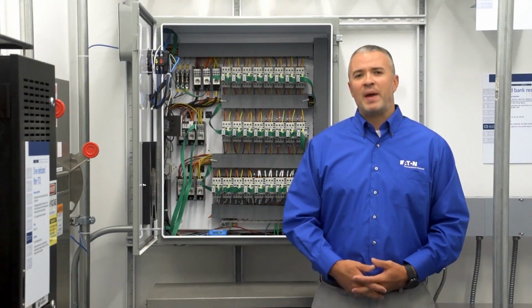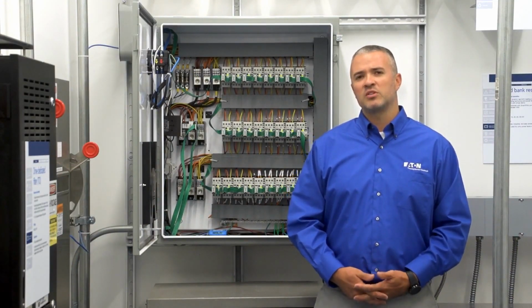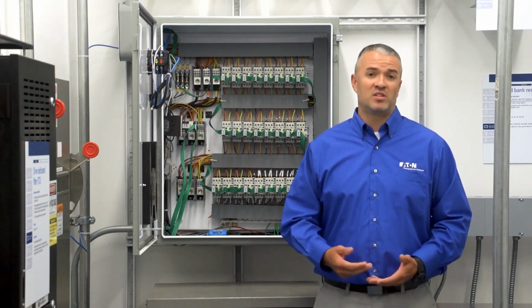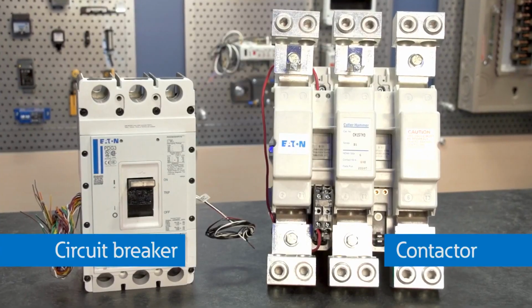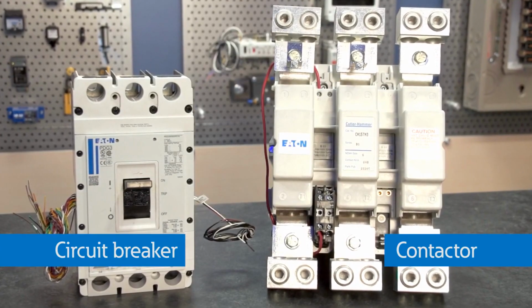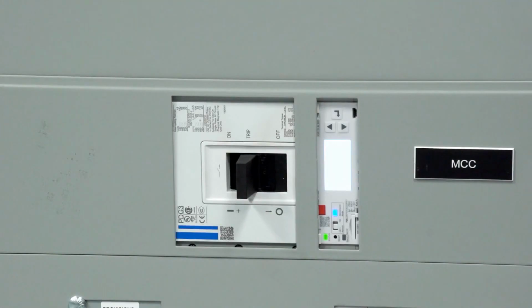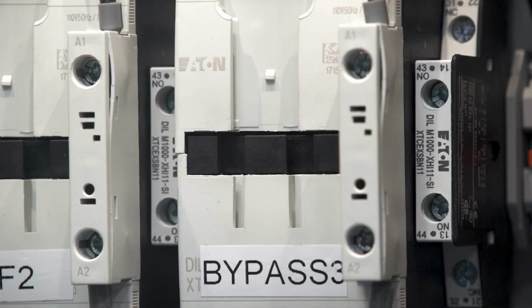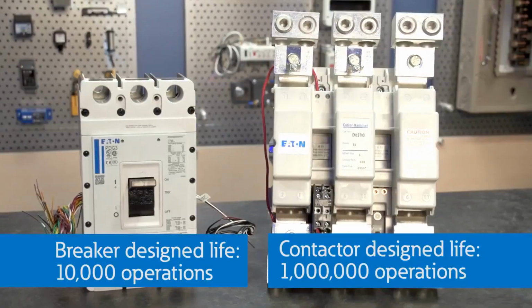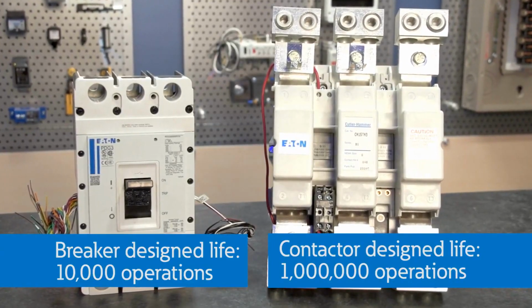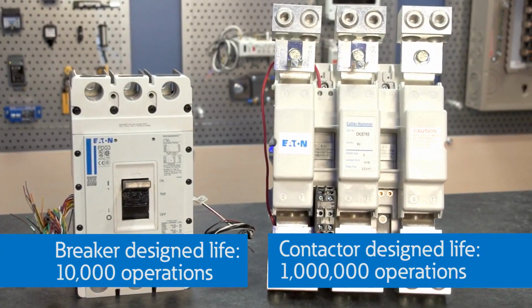Generally, when you think of switching power circuits, you may think of circuit breakers, relays, or starters. What is the difference between a circuit breaker and a contactor? There are many different types and sizes of each, but in general, a circuit breaker's primary function is to interrupt circuits during fault conditions, and a contactor is primarily used to turn on and off loads or control equipment through automation. While a circuit breaker could be used to turn on and off the same loads, it would be considered more of a manual switch. Even more importantly, circuit breakers are typically designed for 10,000 operations and contactors are designed for 1,000,000 operations.